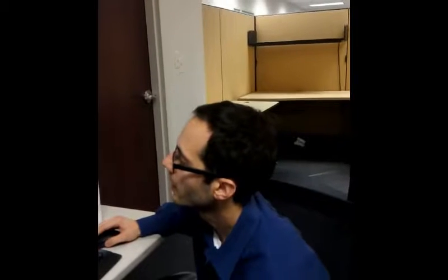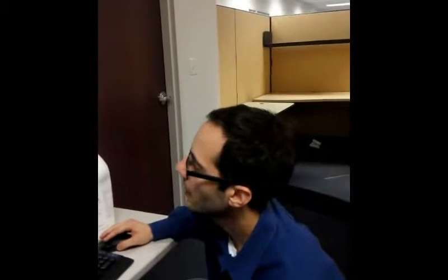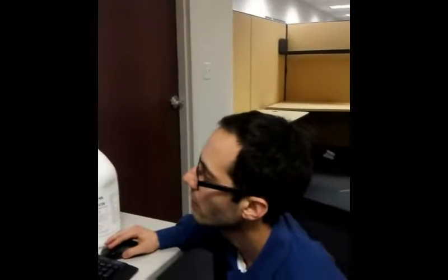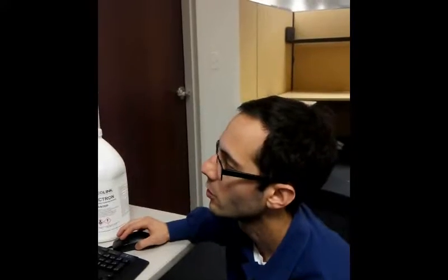Okay. So that's why it warns you at the beginning. It says changing the AP set for this point may result in data loss. You will also need to change the alarm limit set. Do you wish to continue? So seeing this, especially since this is a new install, I'm going to hit yep, no problem, because I'm not going to lose any data.